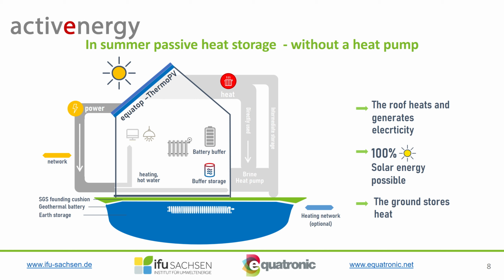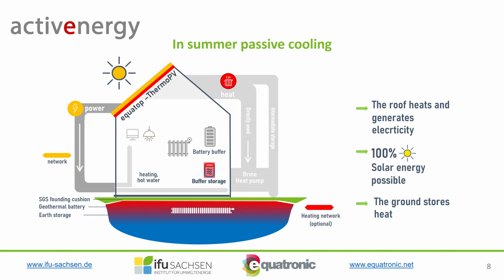In summer, passive heat storage, without a heat pump. When the building envelope generates excess heat, it is transferred directly to the buffer or ground storage tank, without the need for a heat pump. In summer, passive cooling. As long as the underground storage tank is not too hot, natural cooling is possible without an active heat pump. The cooling energy also heats the underground storage tank. In autumn, active cooling. If the underground storage tank gets too warm, the heat pump provides cooling.